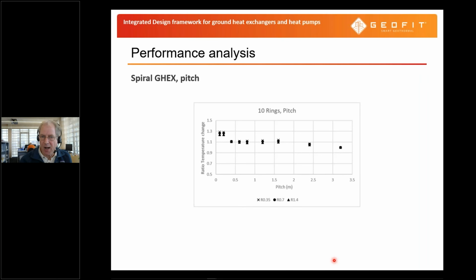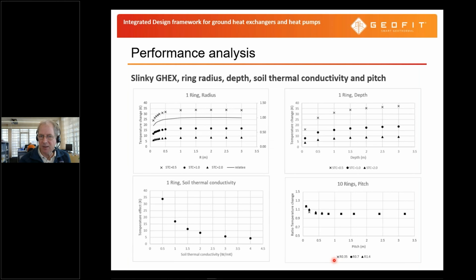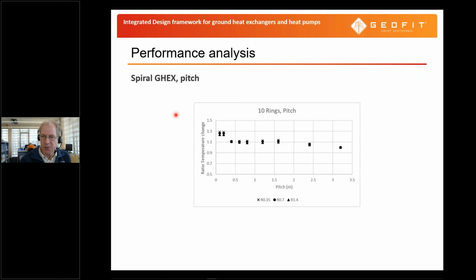Looking at the spiral ground heat exchanger, these were for slinky type heat exchangers like I've indicated here. This is for the spiral type heat exchanger. Obviously, if we look at one ring, the situation will be exactly the same as for a slinky type. But if we look at pitch, then in a slinky type heat exchanger, there is a shift in the horizontal, whereas in a spiral earth basket type heat exchanger, it's a shift in the vertical. So it could be slightly different, but again, you see that at a pitch of around 0.3, 0.4 meters, there is no big effect anymore after that. So there is a kind of minimum pitch that we should consider for these types of heat exchangers.